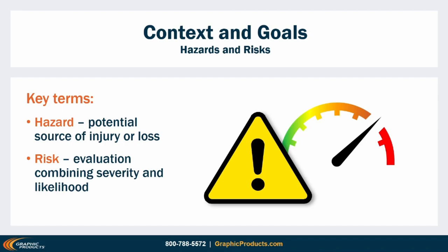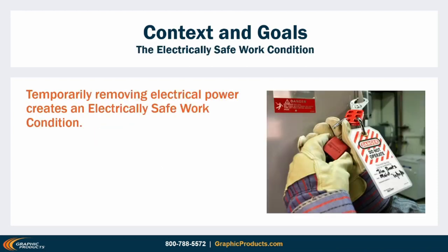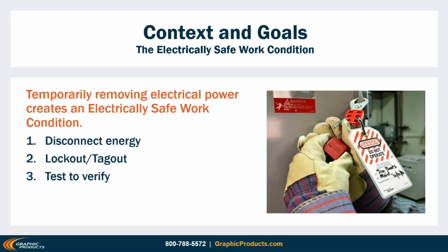However, you can't completely eliminate a risk unless you completely eliminate the underlying hazard. When it comes to electrical safety, that can be done by establishing an electrically safe work condition. With that condition in place, there's no risk of electric shock or arc flash because there's no electrical power — we've removed the hazard. An electrically safe work condition means the equipment has been disconnected from energized parts, locked and tagged in accordance with established standards, tested to verify the absence of voltage, and if necessary, temporarily grounded.